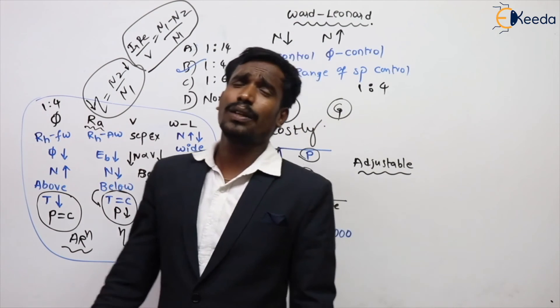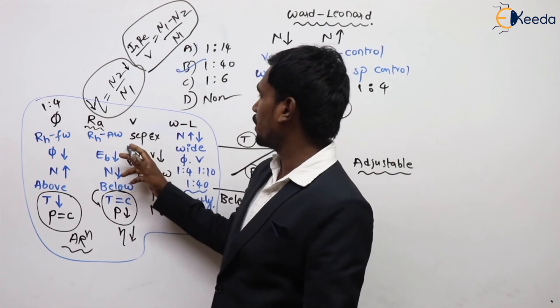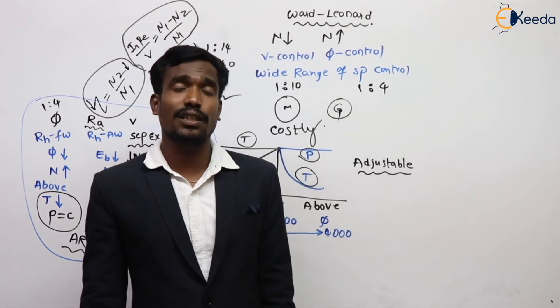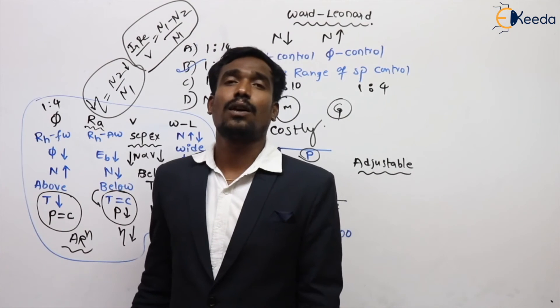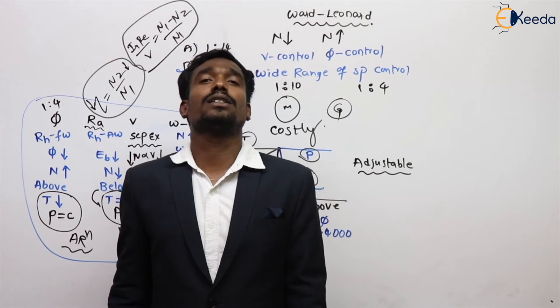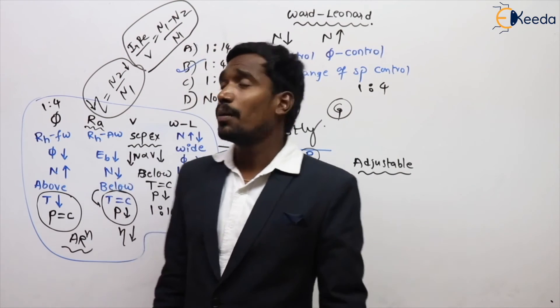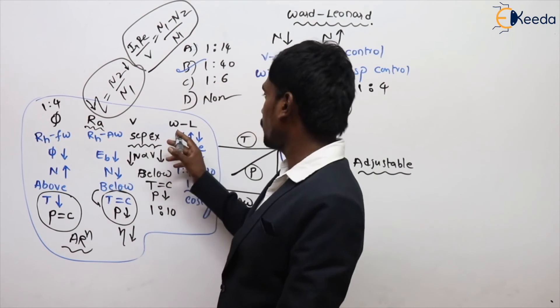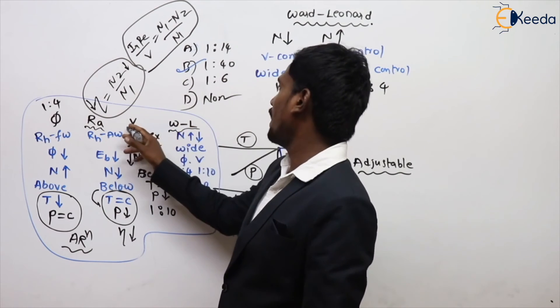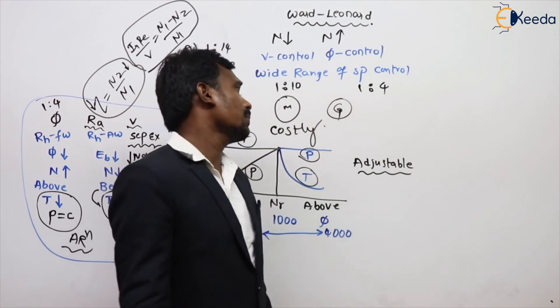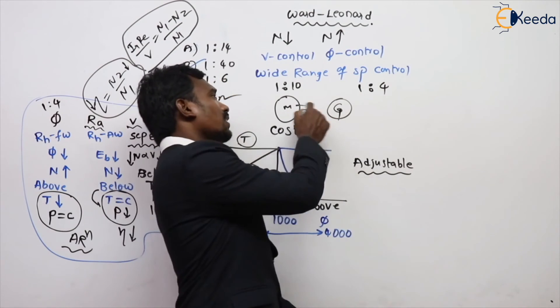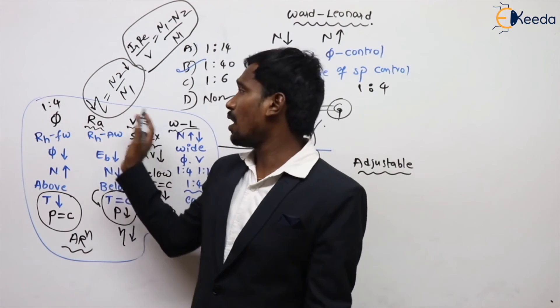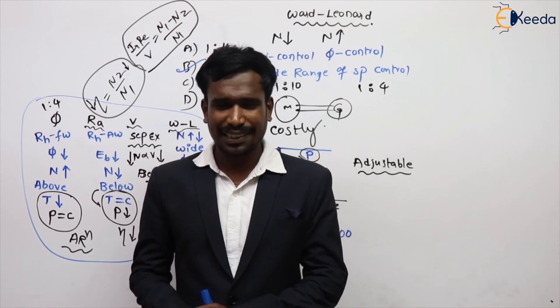What are the disadvantages of voltage control method? This is only applicable for separately excited machines. In a shunt machine, if voltage changes — increases or decreases — there is no change in speed; speed remains constant. But in a separately excited machine, the speed will change. What is the disadvantage of Ward-Leonard speed control method? It is costly because it requires a motor and generator set, making it costly compared to all other methods.